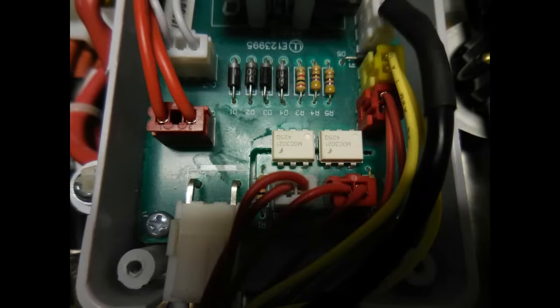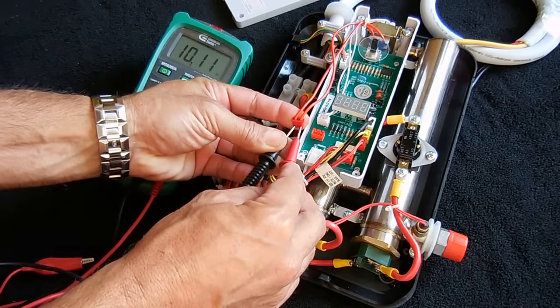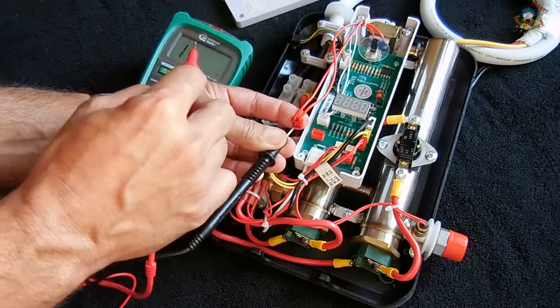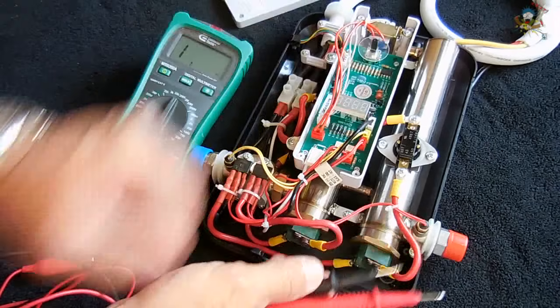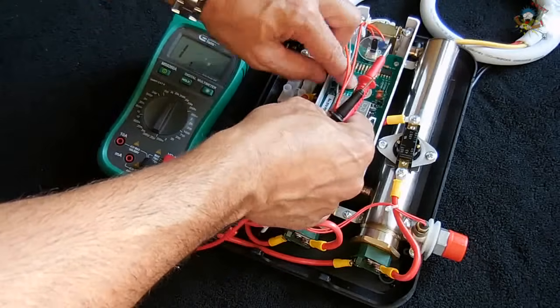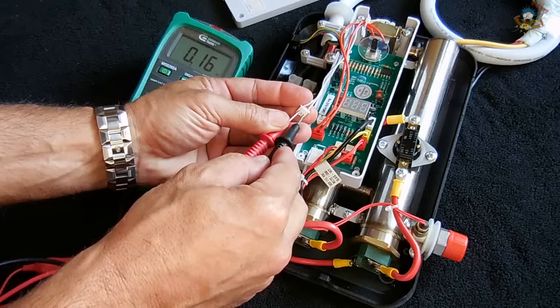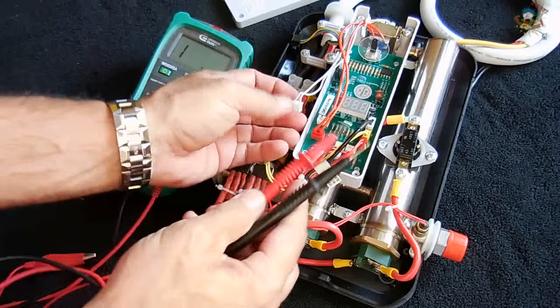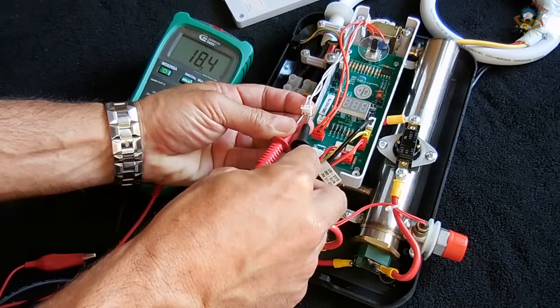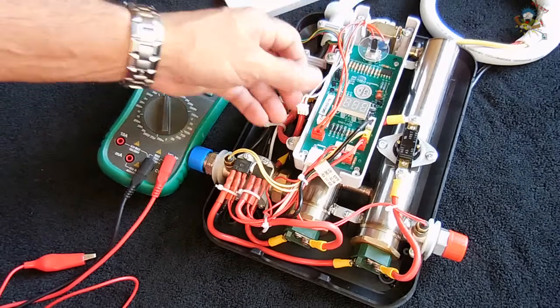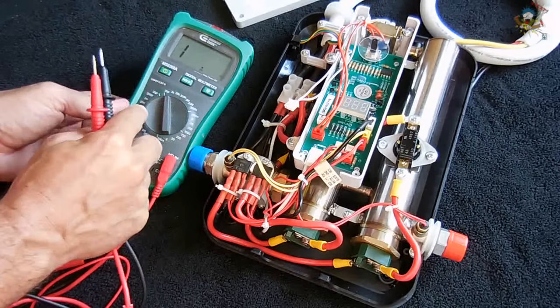So we're going to check the transformer. That's 5,500 ohms. That reading will vary, but when you probe this connection right here you should have a reading. Plug that back in. Next thing going to do is disconnect the secondary side here. Probe that. Should be lower, way lower. So turn this down to the 200 ohm setting. And that's 18.5 ohms. So what that's telling me is that the primary and secondary windings on this transformer are okay.